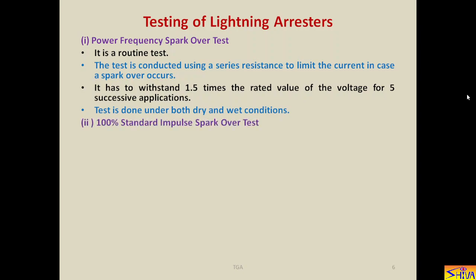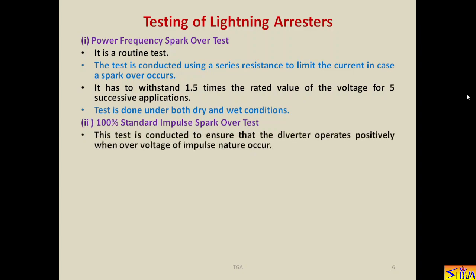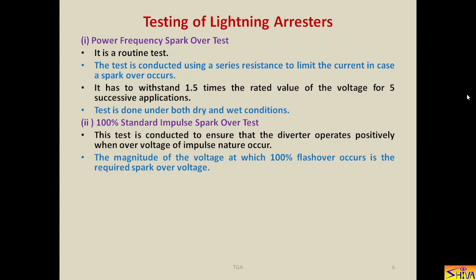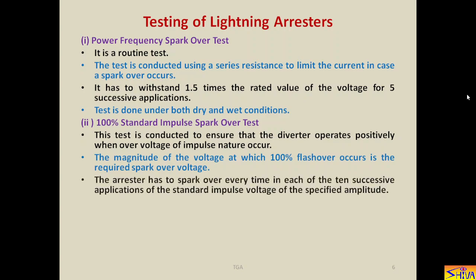Next is 100% standard impulse spark over voltage. So in this case we apply the impulse voltage as per Indian standard, that is 1.2 microseconds should be the rise time with the permissible tolerance, and 50 microseconds should be the tail time with permissible tolerance, and peak value should also be within permissible tolerance. This test is conducted to ensure that the diverter operates positively when over voltage of impulse nature occurs. The magnitude of the voltage at which 100% flashover occurs is the required spark over voltage. The arrestor has to spark over every time in each of the 10 successive applications of the standard impulse voltage of the specified amplitude.